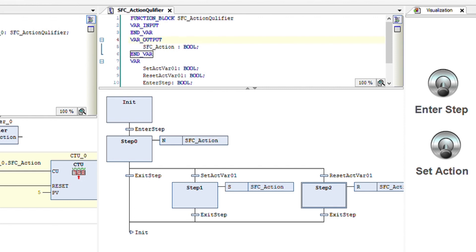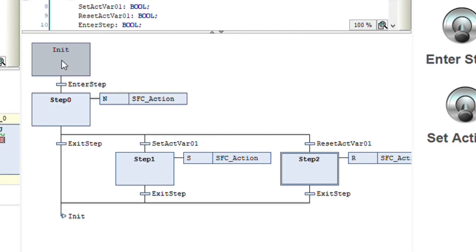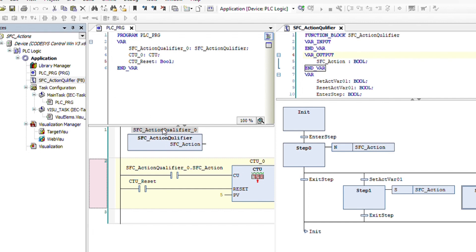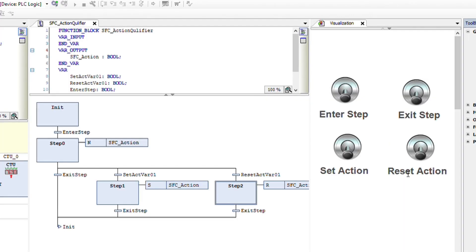Here you can see the way in which it is implemented. I have four steps: init, step 0, step 1, and step 2, and some action. Initially we will start from the init step. Then if enter step becomes true, we'll enter into step 0 and see how the SFC action will be executed by changing this qualifier, which is initially set to N. In the main program PLC_PRG, I have one instance of this function block. In a simple visualization, I have placed some switches to provide values for enter step, exit step, set action variable, and reset action variable.